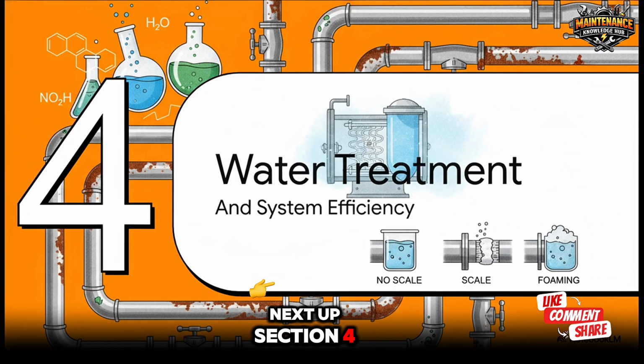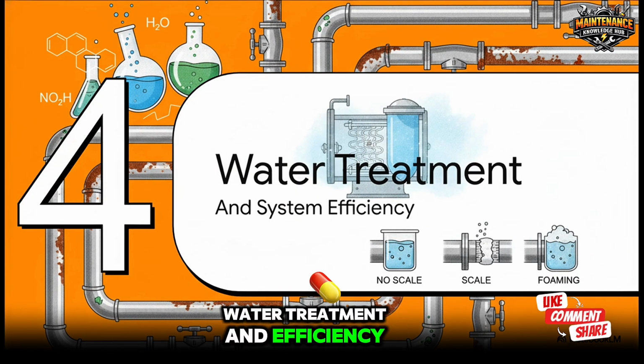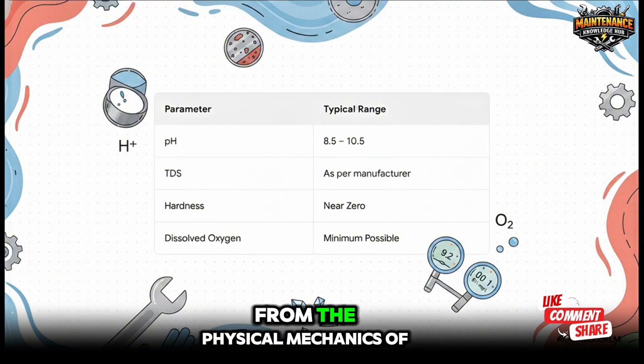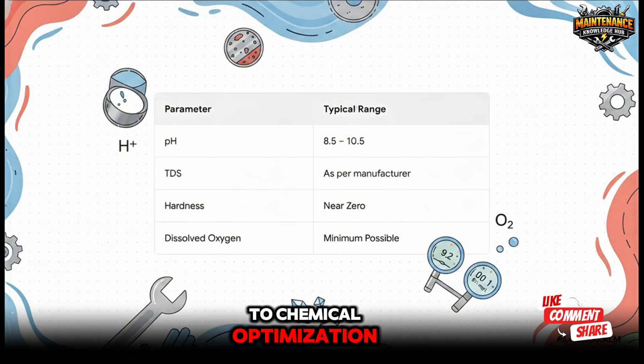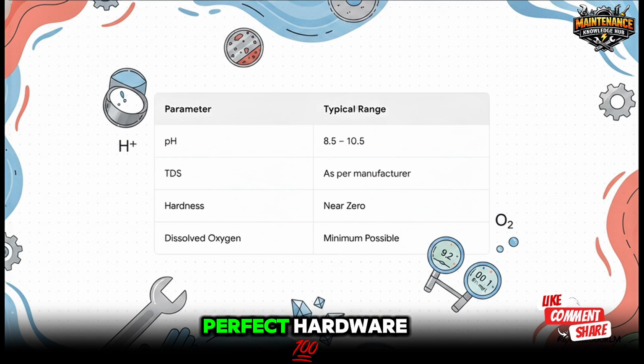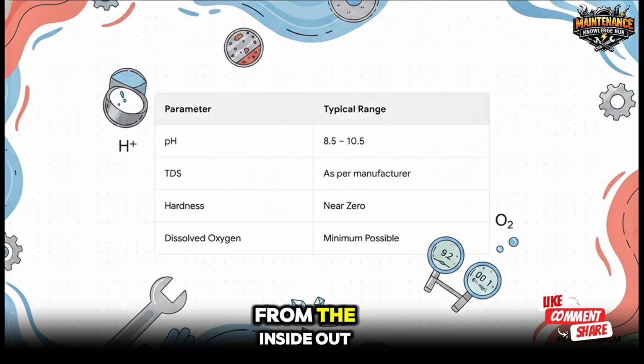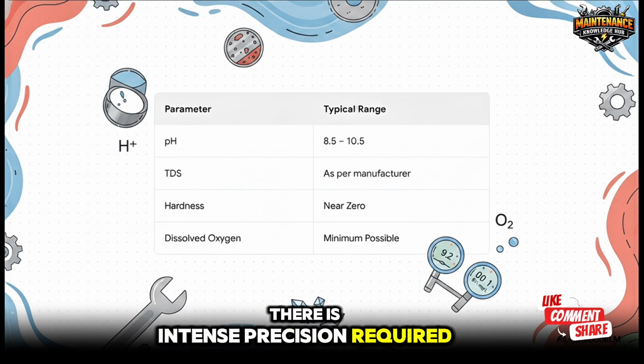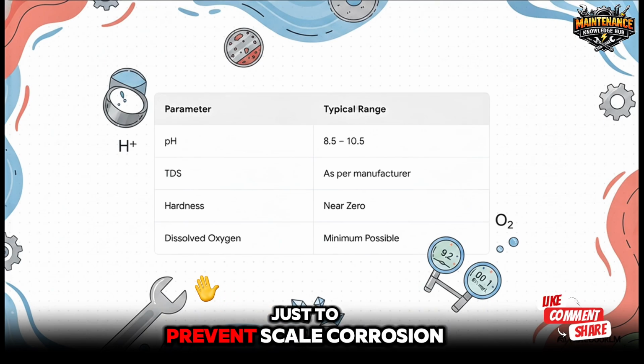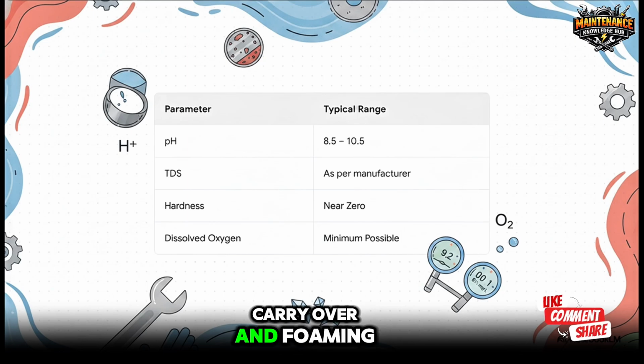Next up, Section 4, Water Treatment and Efficiency. Let's pivot for a second from the physical mechanics of the boiler to chemical optimization. You could have absolute perfect hardware, but if your water chemistry is wrong, the boiler will literally destroy itself from the inside out. There is intense precision required for these chemical parameters, just to prevent scale, corrosion, carryover, and foaming.